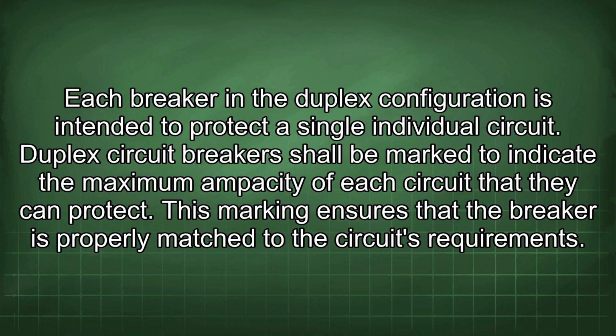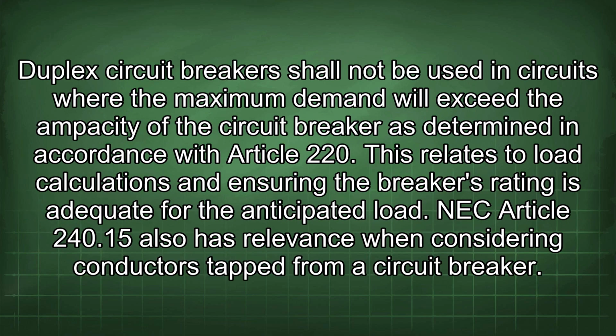Duplex circuit breakers shall be marked to indicate the maximum ampacity of each circuit that they can protect. This marking ensures that the breaker is properly matched to the circuit's requirements. Duplex circuit breakers shall not be used in circuits where the maximum demand will exceed the ampacity of the circuit breaker, as determined in accordance with Article 220. This relates to load calculations and ensuring the breaker's rating is adequate for the anticipated load.